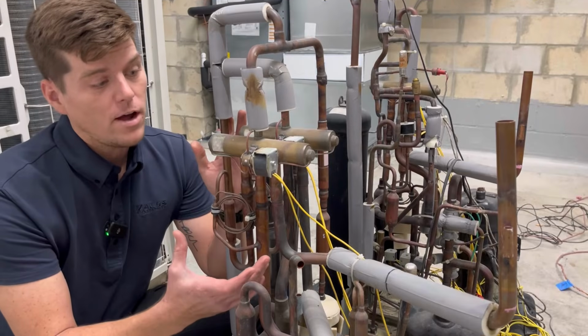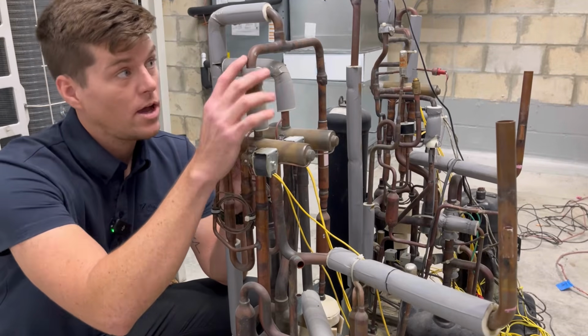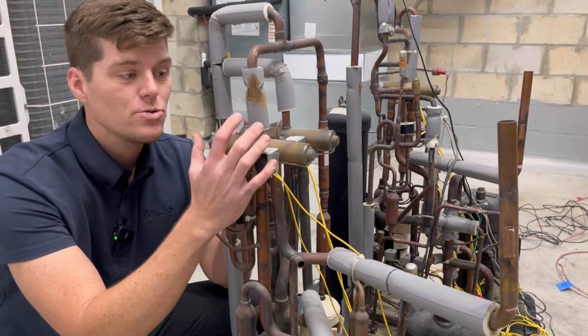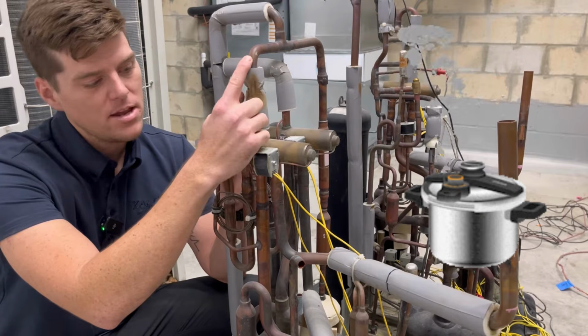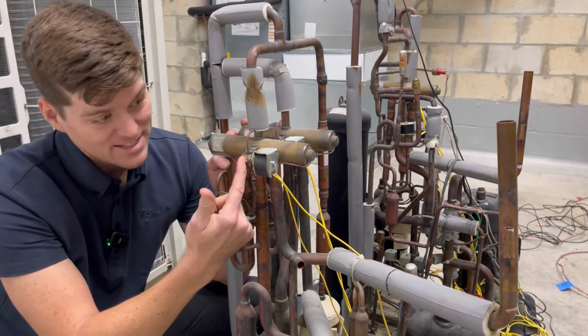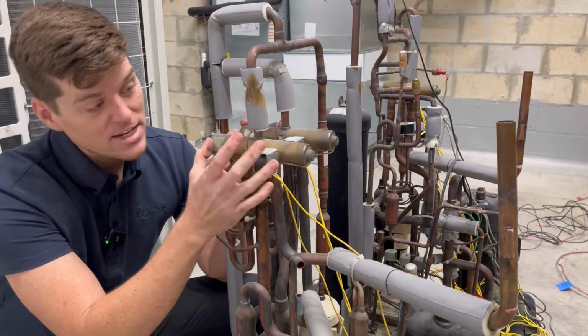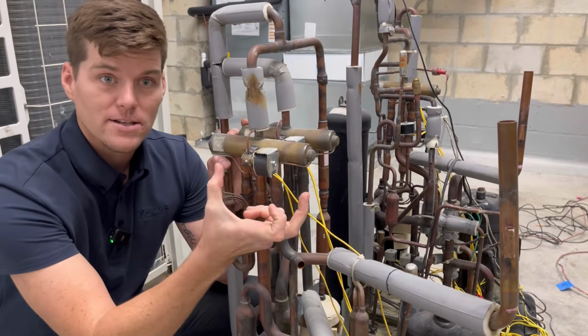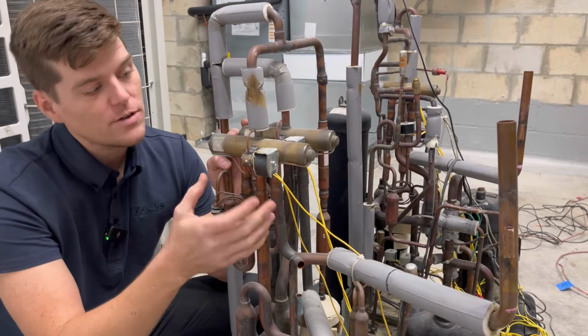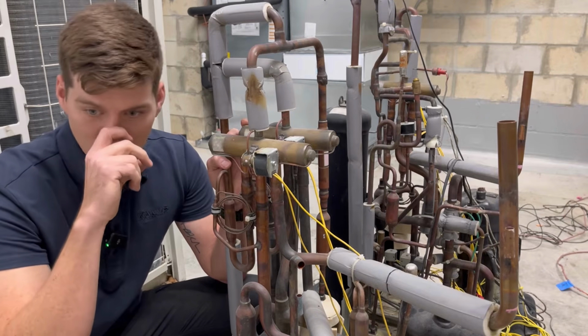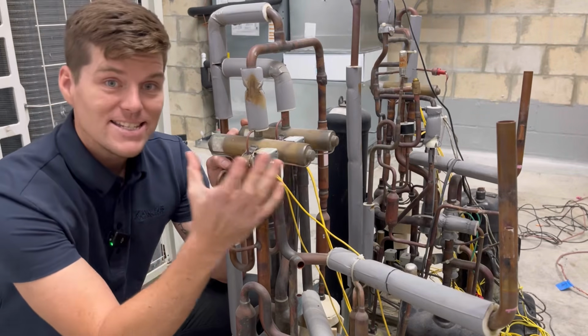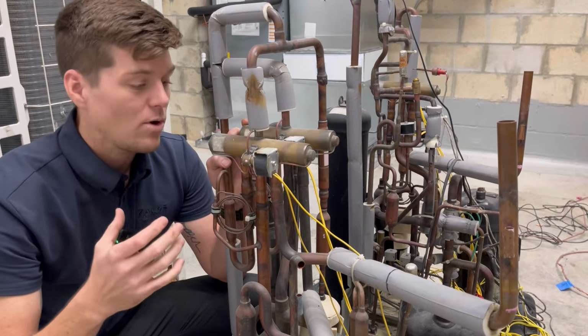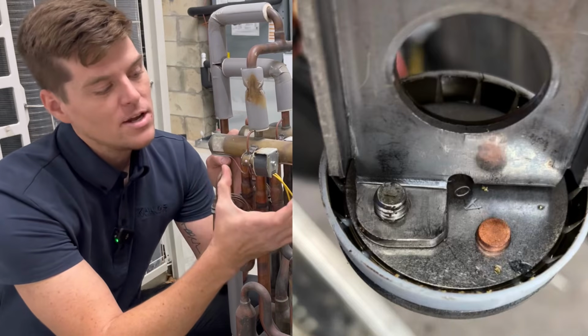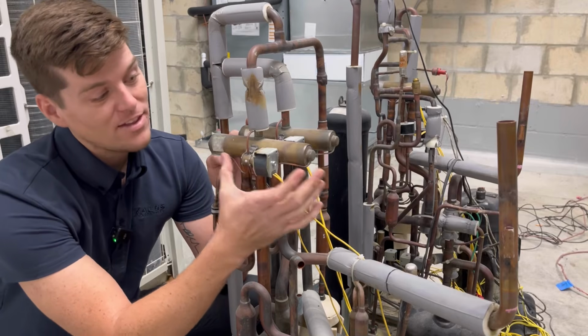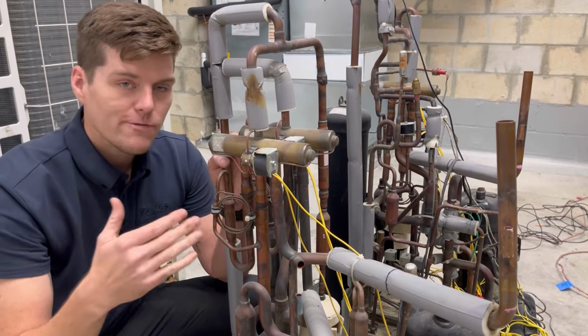Notice here with a four-way valve that the top portion here, or the smaller line that you see that comes off the top of this four-way valve, is your discharge line. This means that this is always in a high pressure, right, high pressure, high temperature state. We need that because that's where it takes the gas from to actually pressurize either side of the cylinder to shift that internal mechanism. So what happens when it doesn't shift? Well, if it doesn't shift, there could be sand, contaminants, you name it, built up inside of this valve that isn't allowing it to shift or even displaced. We've had ones where screws have come out of the actual assembly to where they don't line up anymore. They get stuck in the chamber here and they won't shift. Right? That's a four-way valve that has failed.